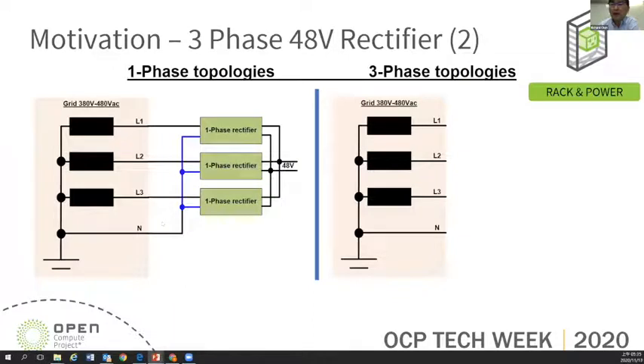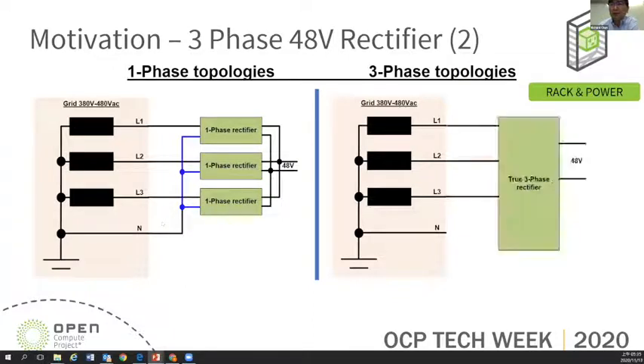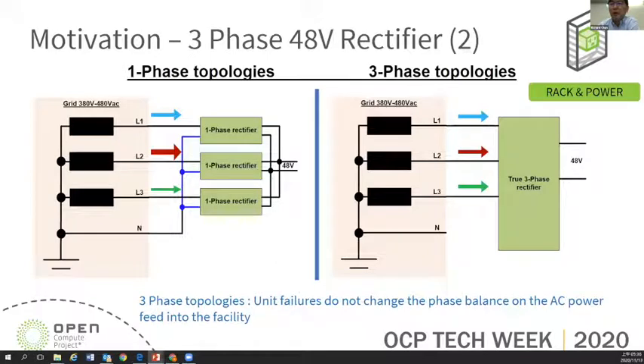The other thing is that we consider the phase balance. When we do the single phase topology, for phase balance we need to utilize the single phase power supply output current sharing. Then that will impact the input current sharing. If in some load conditions the current sharing is not good, the phase balance will also not be good. Also, we need to consider abnormal conditions. If some of the power modules fail, it will also impact the single phase topology current sharing. However, if we do the 3-phase design, the 3 phases are already controlled in the 3-phase rectifier, so we do not have this phase balance concern.